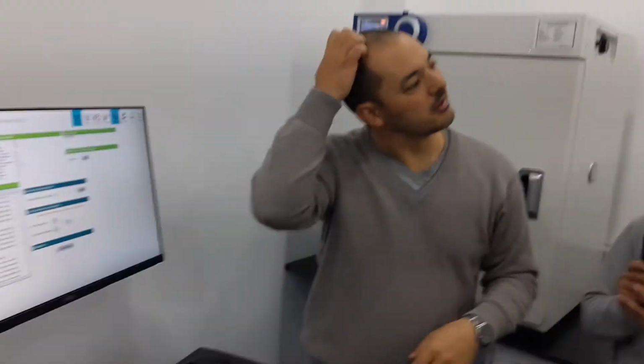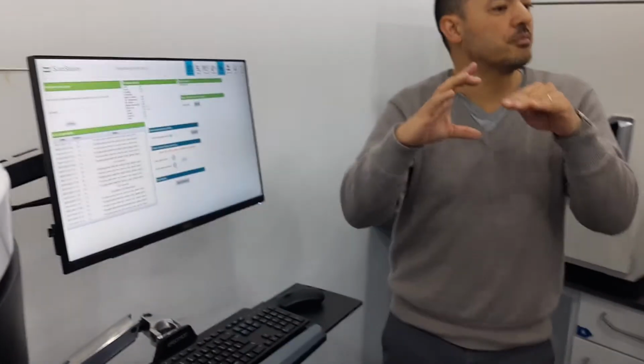And yeah, you see it? The best is to be on the side of the carousel because the petri dishes are on this side, so that's the real important observation. We have the same opening like this? Yeah, on the other side, exactly. So if the sensor drifts a little bit, you don't need to change the sensor, but you might change the offset and put it back on track, like a little threshold.